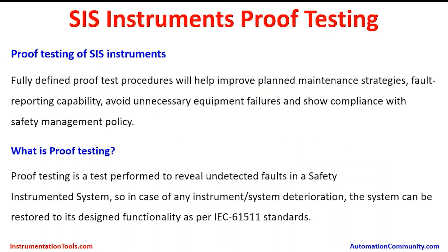Proof Testing of Safety Instrumented Systems Instruments. Fully defined proof test procedures will help improve plant maintenance strategies, fault reporting capability, avoid unnecessary equipment failures, and show compliance with the safety management policy. Each plant will have a safety management team to ensure the protection of the people working in the plant as well as the facilities available. The proof testing has to go as per the maintenance procedures and get it rated by the safety management team, which may be called the Health, Safety and Environment team, or named differently in each company.